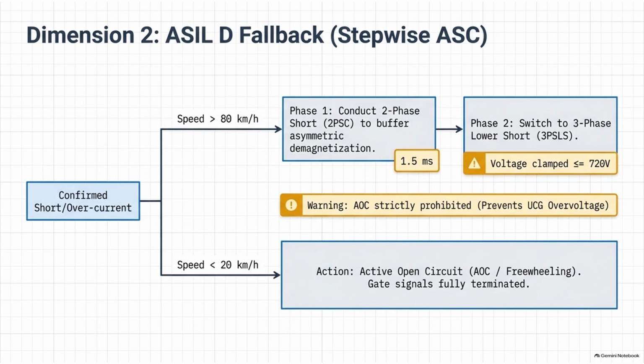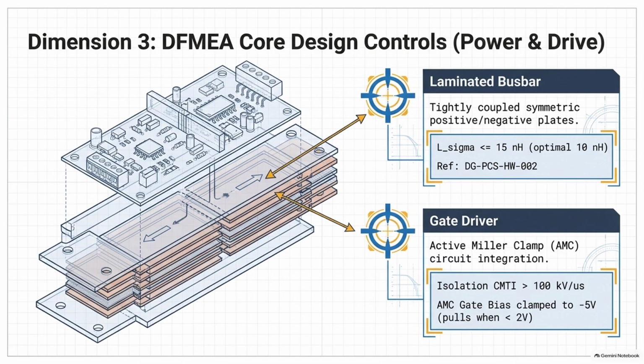But you know, managing a fire is still managing a fire. Catching a catastrophic fault in a microsecond is great, but mathematically eliminating the conditions that allow the fire to start is engineering perfection. Absolutely. And that brings us to Section 4 of the specs, the DFMEA, Design Failure Mode and Effects Analysis. How do they architect the physical hardware to choke these physics out before they even happen? Well, you have to stack the physical environment heavily in your favor. Let's revisit that parasitic inductance that causes the overvoltage avalanche. The di/dt is a given. You can't change how fast the GaN switches without losing your efficiency. So the only variable you can control is the inductance of the metal itself.